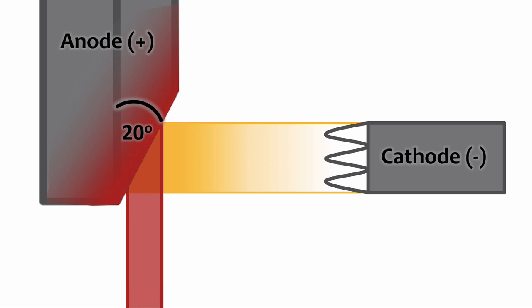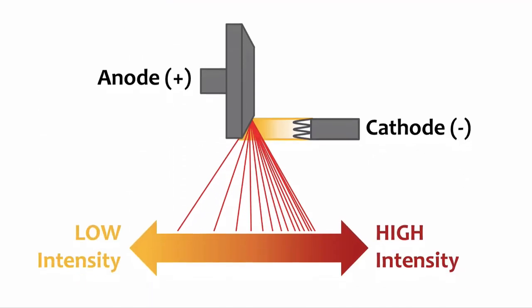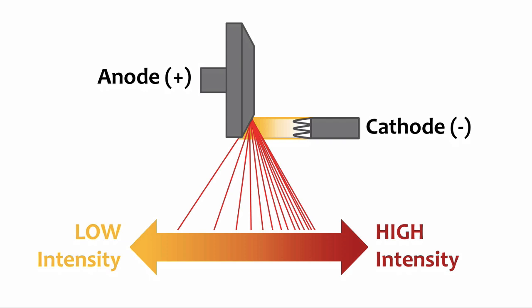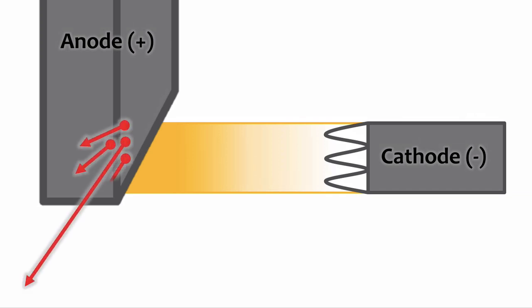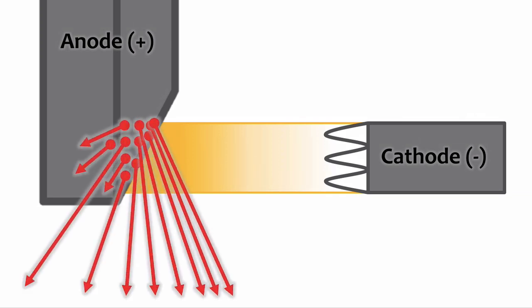Unfortunately, the angled anode does have one negative consequence. The angle of the anode causes a variation of the beam's intensity across the x-ray field. Specifically, there are fewer x-ray photons on the anode side of the beam compared to the cathode side, so the cathode side has the higher intensity and the anode side has the lower intensity. This happens because x-ray photons are created throughout the anode, and some photons created deep in the anode get absorbed within the anode heel. As a result, the x-ray beam has fewer photons on the anode side — that's the definition of the anode heel effect: decreased x-ray beam intensity on the anode side of the beam.